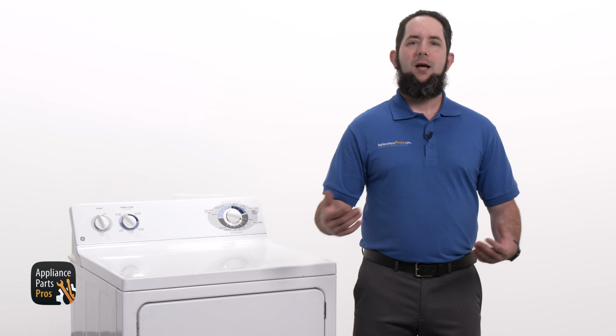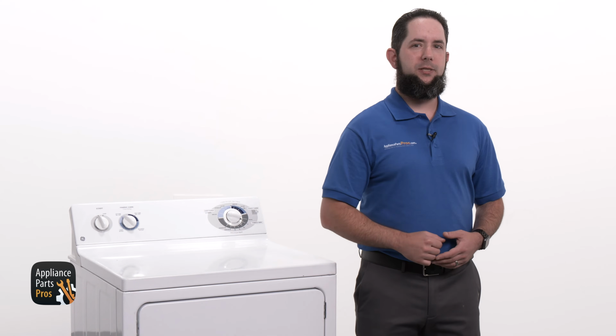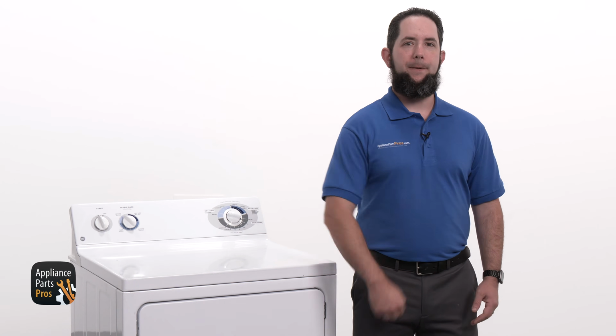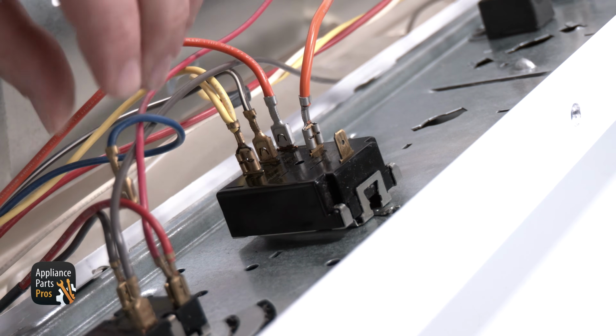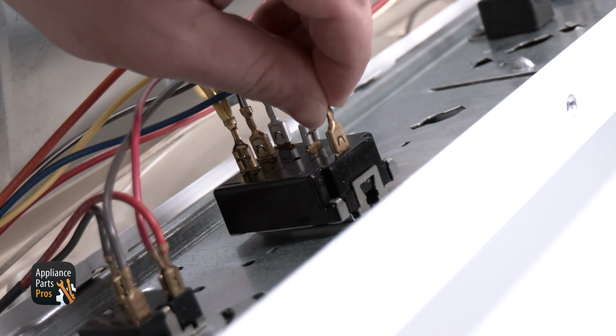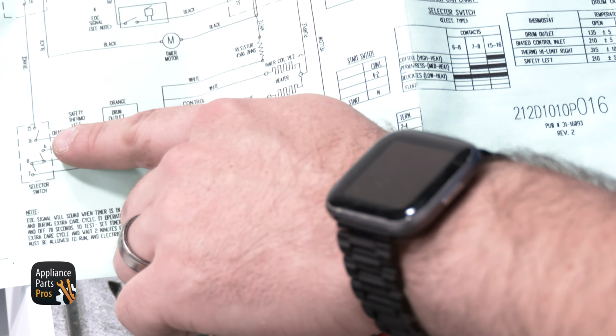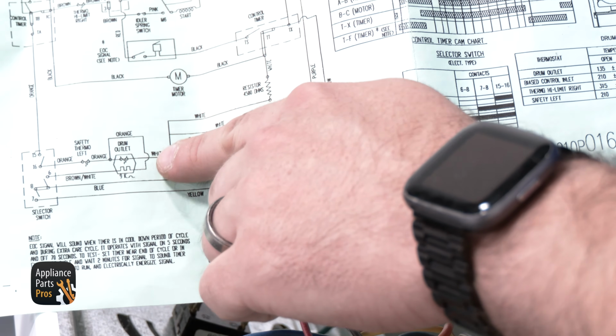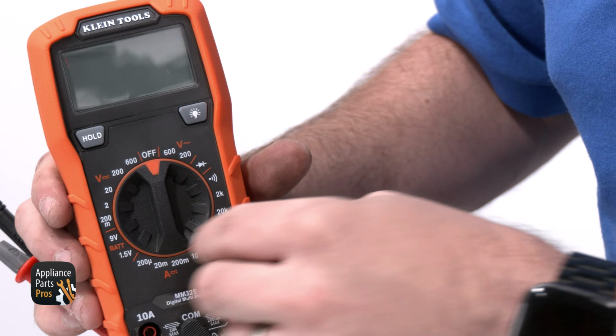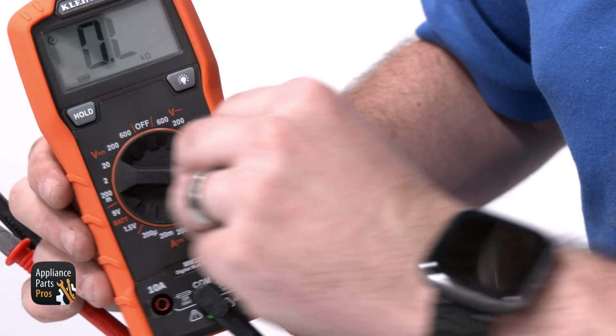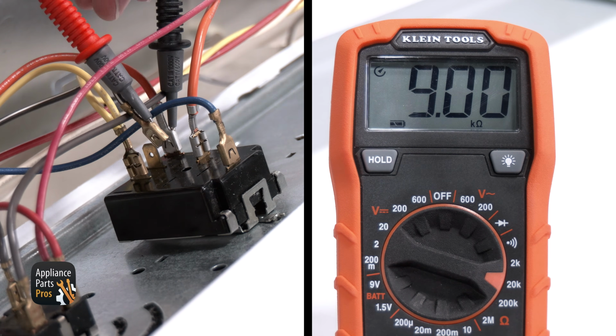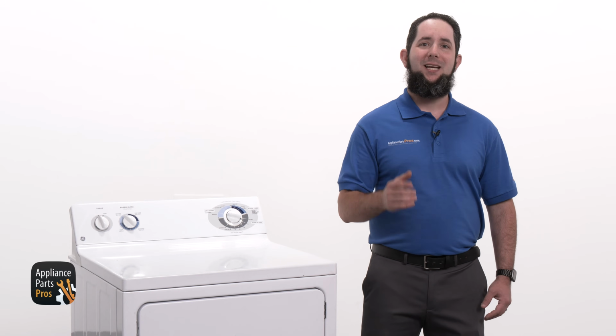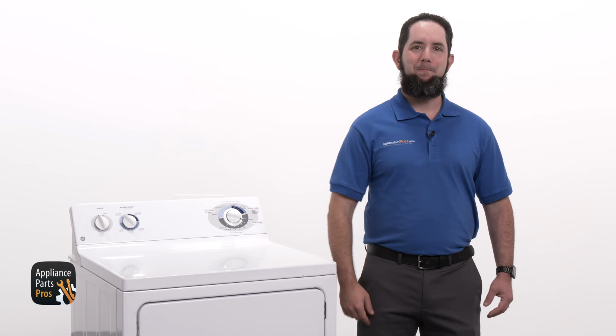And guess what? I know a shortcut to test all the thermostats using just the wires right here. First, reconnect the wires at terminal 16 and 8. If we look at our wiring diagram, we can follow the orange wire at terminal 16 to see that it should measure 9 k ohms of resistance when it's tested to the brown wire with a white stripe and then to the blue wire. But I'm still going to show you how you can test each thermostat directly in case you prefer to do it that way.